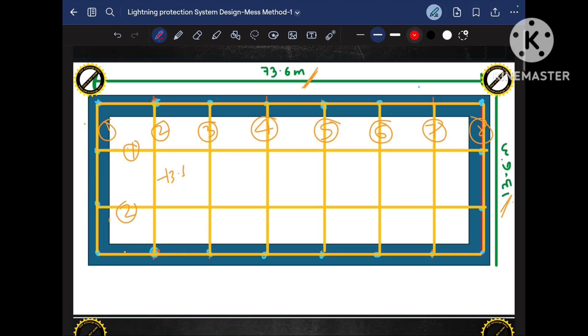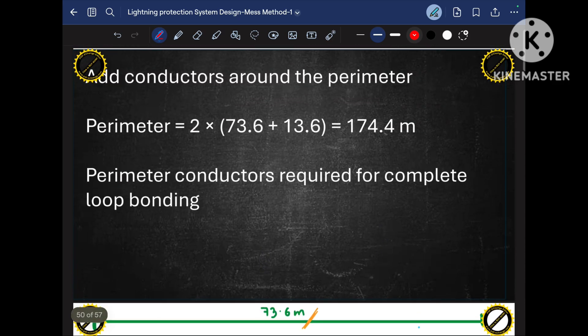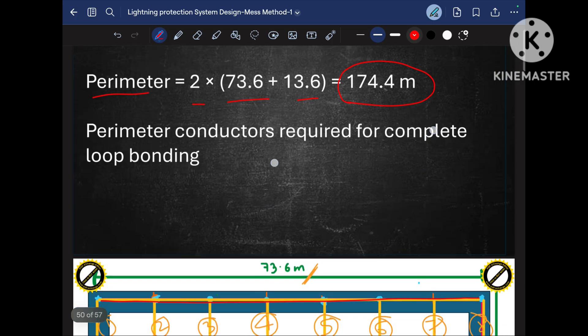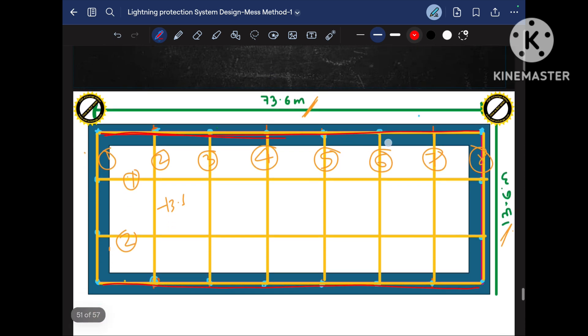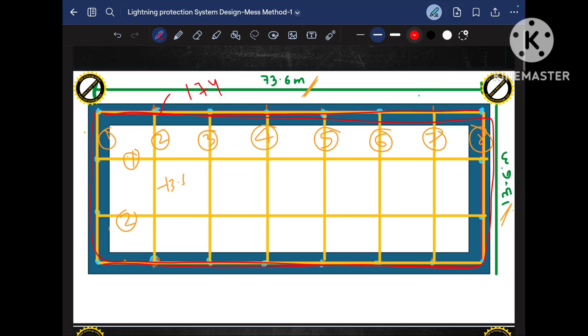You can see there is a conductor running along the perimeter here and here. If we know the perimeter of the building, we can determine the length of that perimeter conductor as well. The perimeter is calculated as 2 × (length + width), giving 174.4 meters. So in the MESH method, we also run a conductor around the perimeter of the building, which is approximately 174 meters.